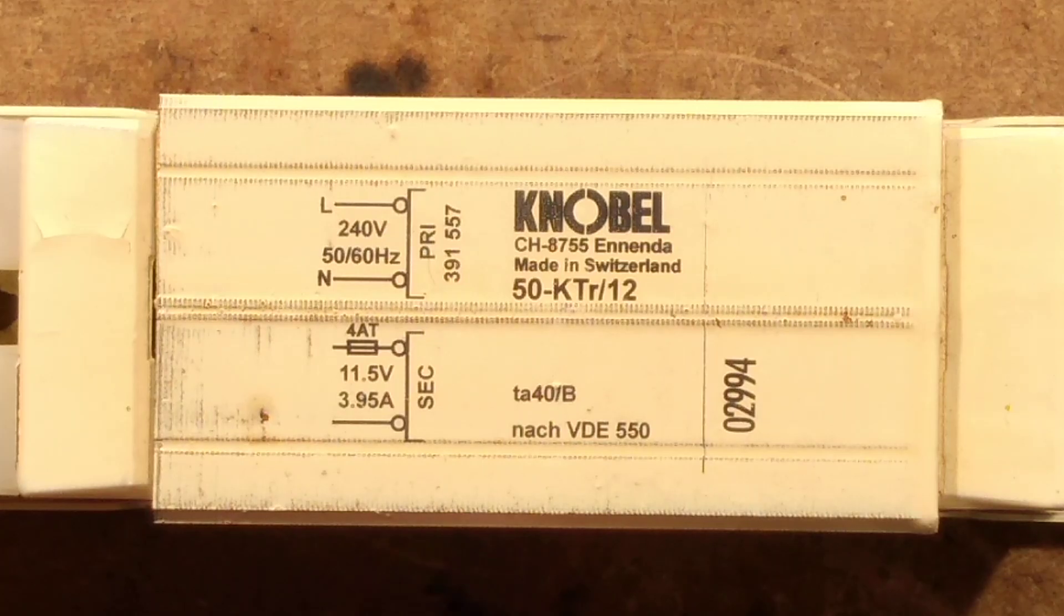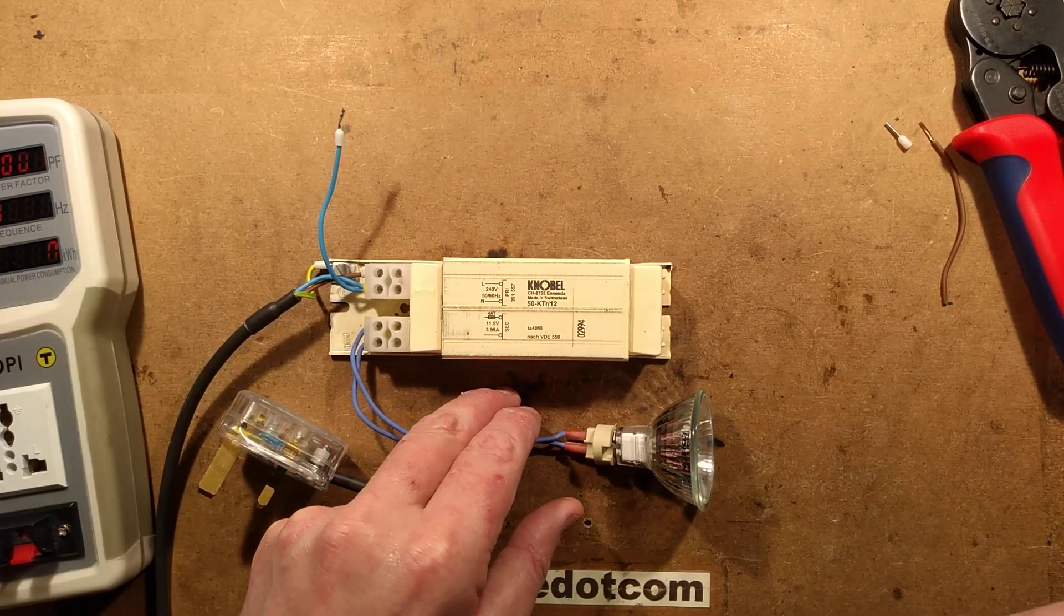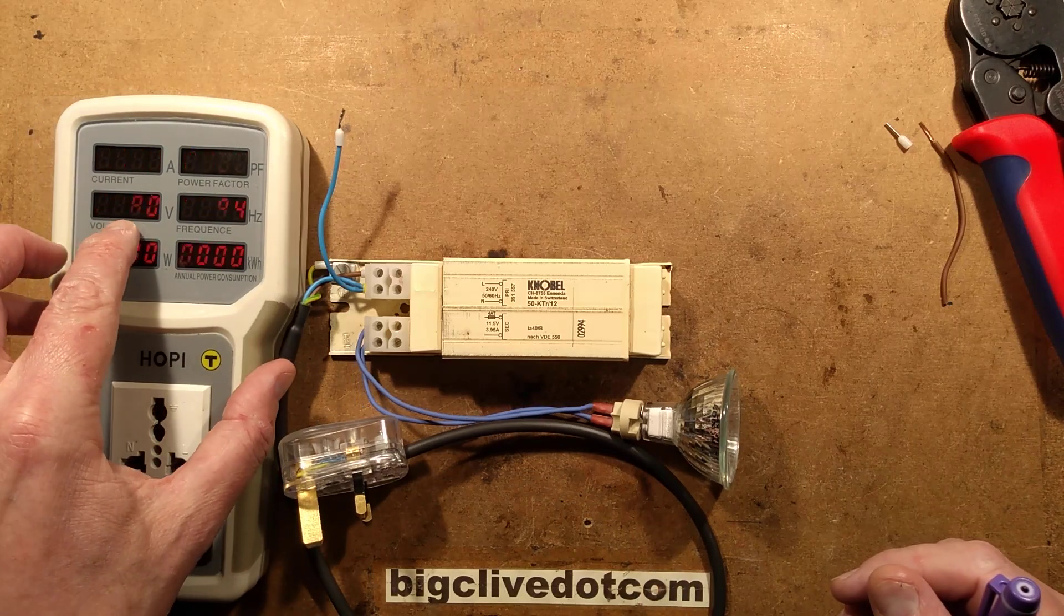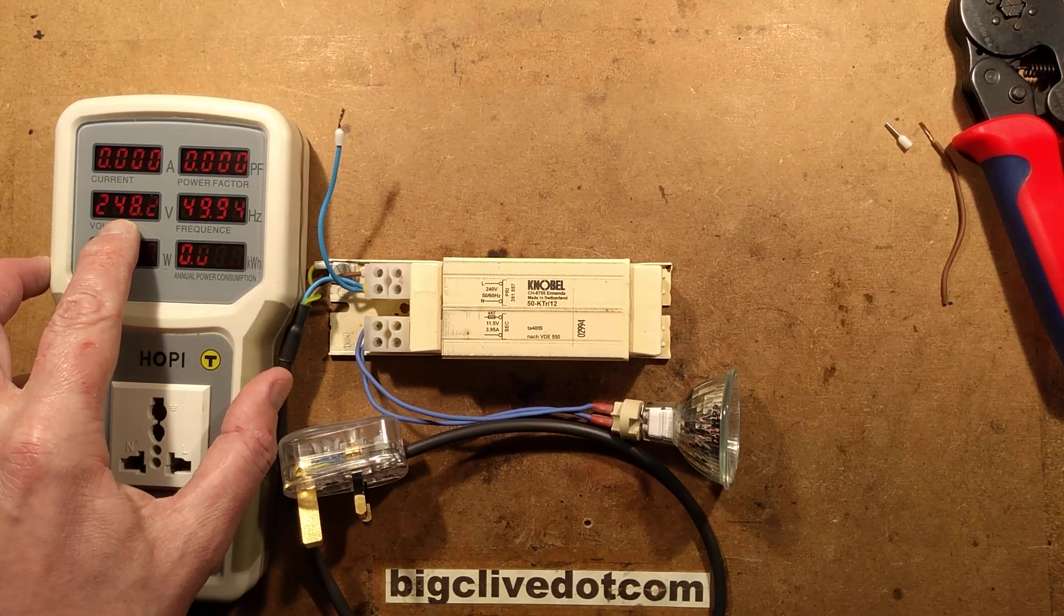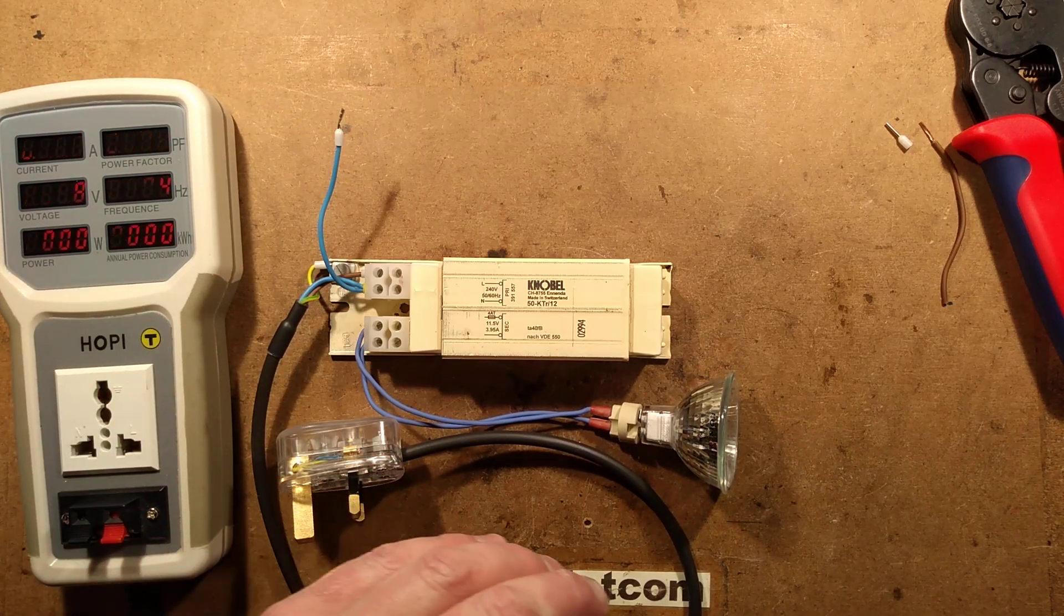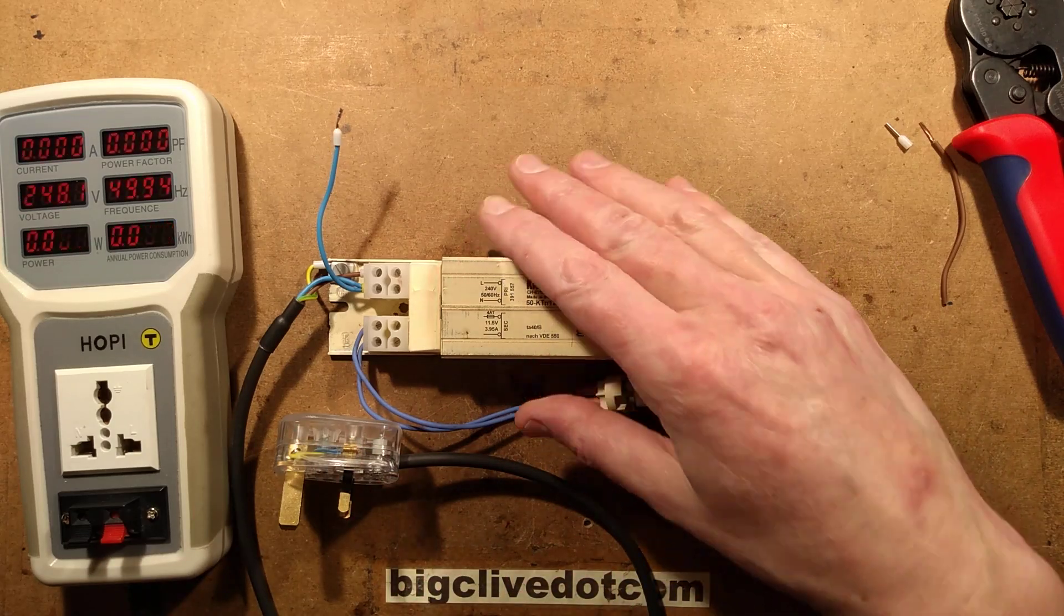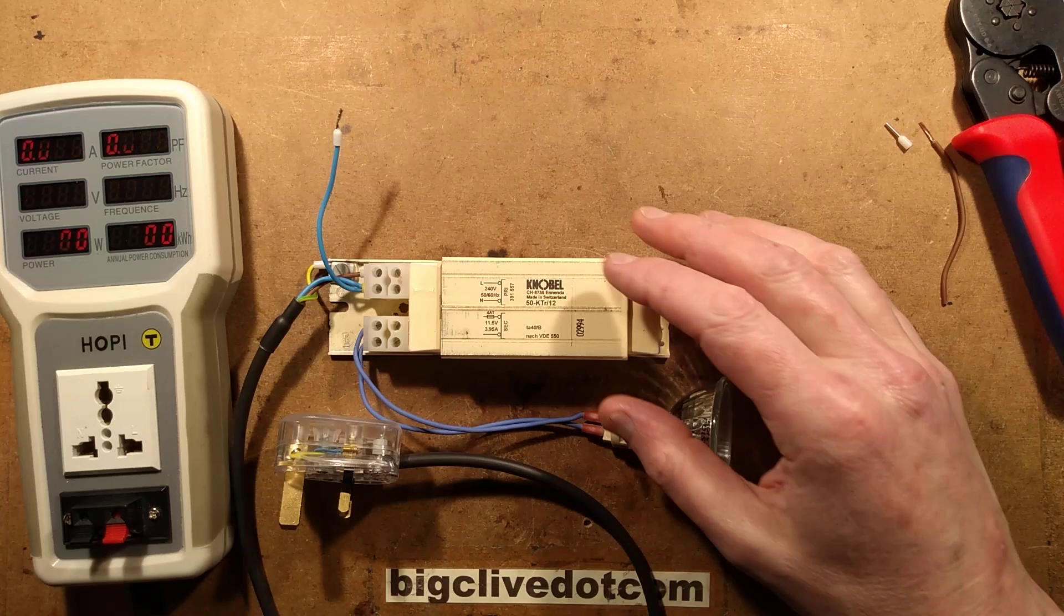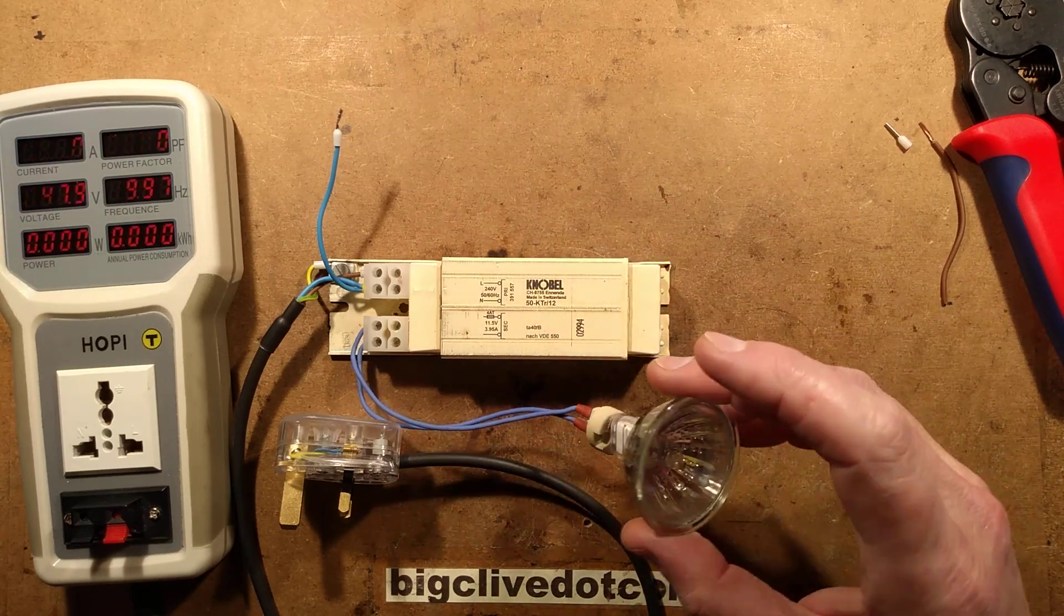In reality, the supply voltage at the moment is actually 248 volts here. Yeah, it's quite high. That is peaking. That's because it's quite late at night. Everybody's gone to bed. I'm the only person on the transformer locally, apparently, and the voltage has floated up. That's what happens to transformers. As you load them down, the voltage drops. It's called internal regulation of transformer.